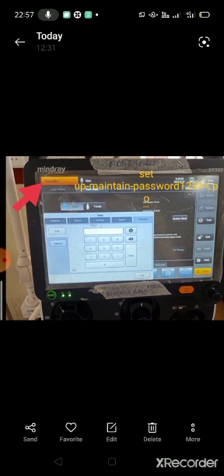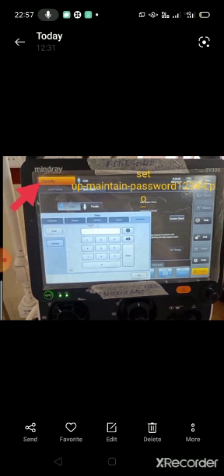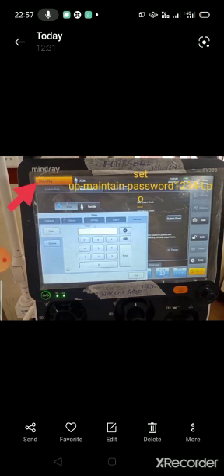So let me brief you on what you have to take care of when you are connecting the SV300 ventilator. One is, when you are connecting the SV300 in portable mode, never fill the humidifier bottle with water, and you have to change the settings to LPO mode. So these two things you have to do when you are using the ventilator in portable mode. And when you are using the ventilator in standalone, you have to connect the O2 hose to the wall. One more thing, when you are connecting the ventilator in portable mode, be sure you have enough battery backup with the ventilator. The battery should be fully charged. Otherwise, in between shifting the patient, the ventilator may switch off. So ensure the battery is fully charged, or you have enough charge in the battery.